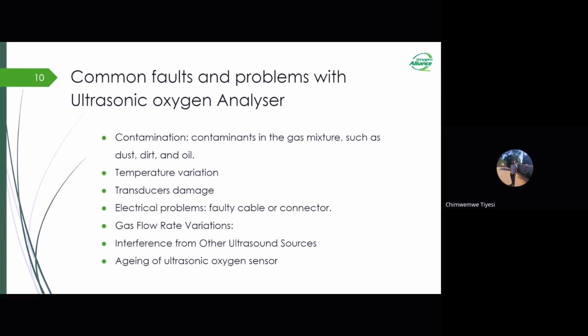But if these sensors are not functioning correctly, or temperature varies beyond the compensation range, it can lead to inaccuracies. Another thing that may affect the accuracy of measurement is vibration and mechanical shocks. Ultrasonic analyzers are sensitive instruments, especially the transducers, since they are made up of crystals. Exposure to excessive vibration or mechanical shock can damage transducers and lead to measurement errors as well. Another cause of errors or display inaccuracies is cable and connection issues. Faulty cables or poor connections between the analyzer and the components can lead to signal loss or interference, which can also result in inaccurate readings.